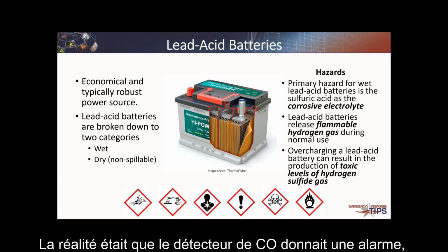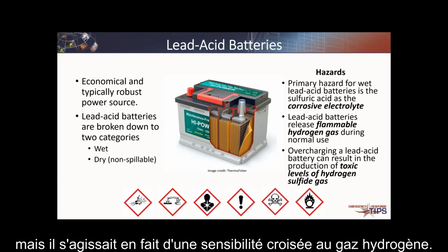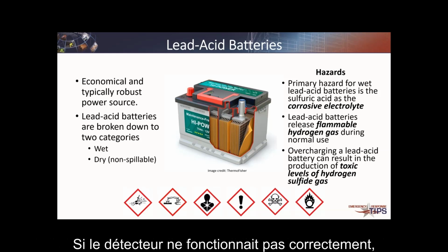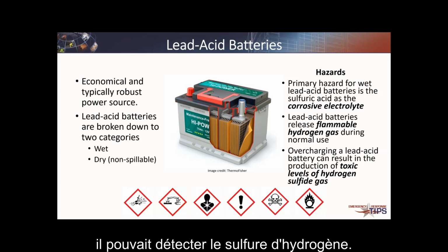So reality was the CO sensor was giving them alarm, but it was alarming because it was cross sensitive to hydrogen gas. Now, if it wasn't working properly, then you get the hydrogen sulfide gas.